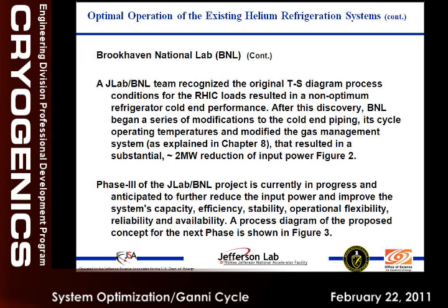We went on a weekend, we did that, and it dropped. Basically we changed it from fixed pressure to floating pressure. Zero investment except they bought 2 tickets for me and Pete. And we dropped 2 megawatts that day. At Long Island, it's not 4 cents a kilowatt, and they were rewriting their negotiations. That's when, with some of the arguments I gave you, they said, oh, put it back. We have to retrain our operators. It's going to cut into our availability.